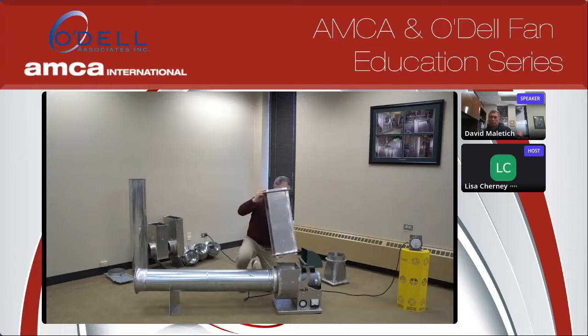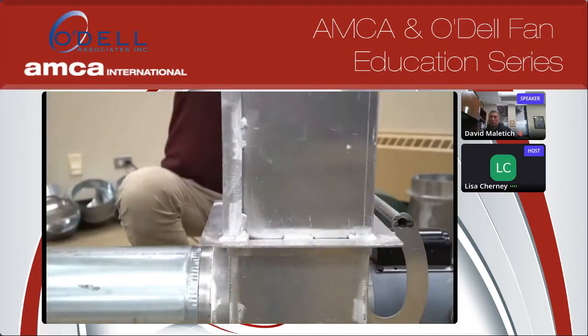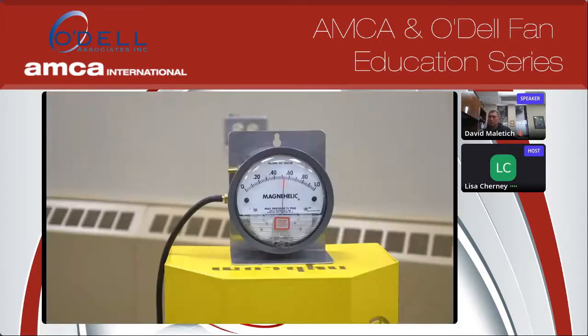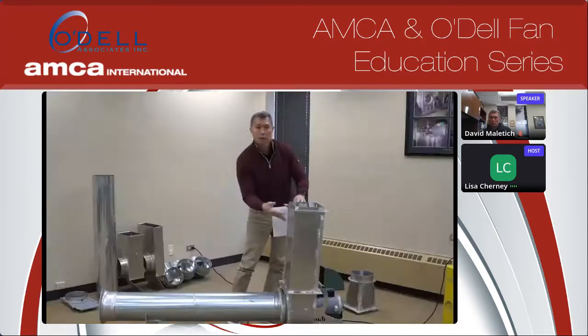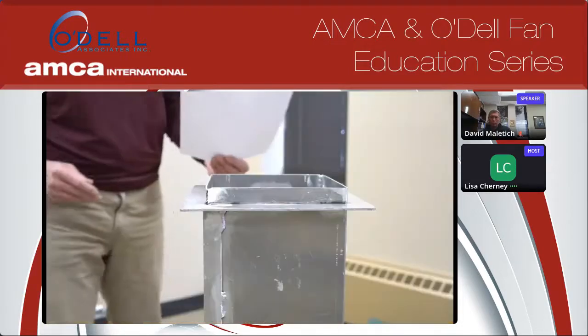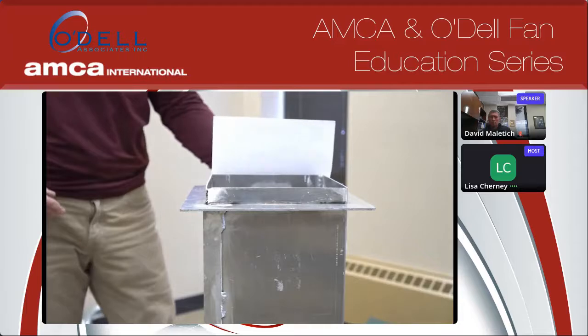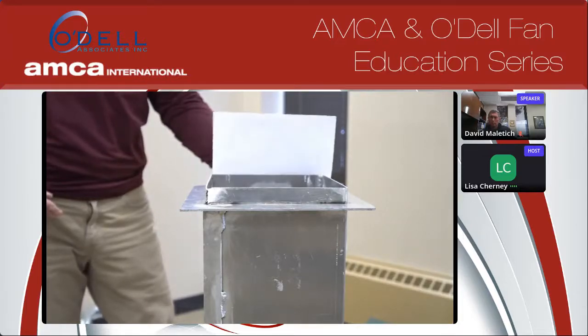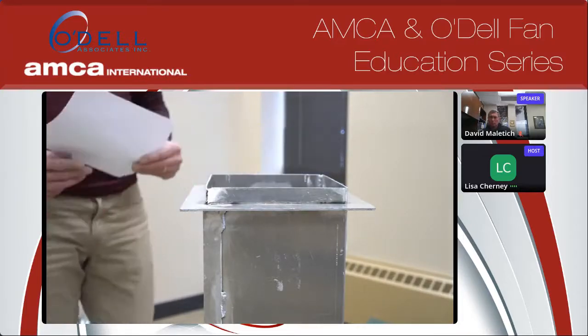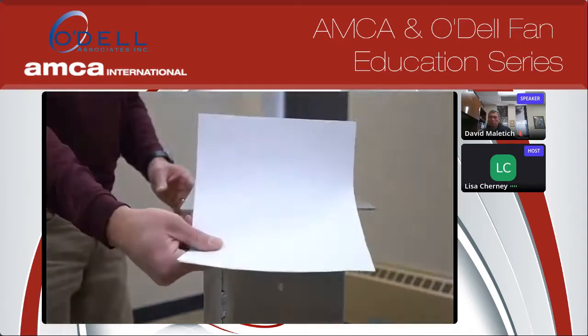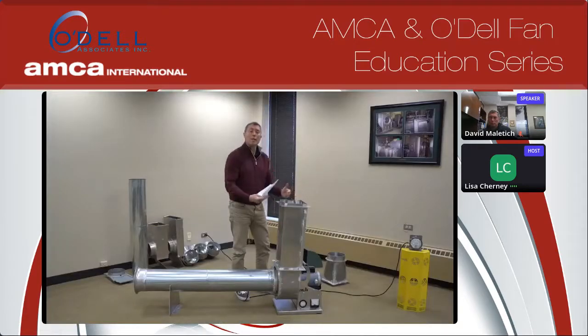Putting this ductwork on the outlet of the fan, notice that there's a change in performance when you look at the Magnehelic gauge, that it's actually dramatically improved. And the reason it's improved is that the air velocity profile has gone through this piece of ductwork and has actually evened out. So if I look at it here, put the same piece of paper here, notice it blows the piece of paper up. It's no longer negative pressure at this section. And if I do the same thing at the other side, it's positive pressure as well. So now we have laminar flow, and that laminar flow results in increase in performance.